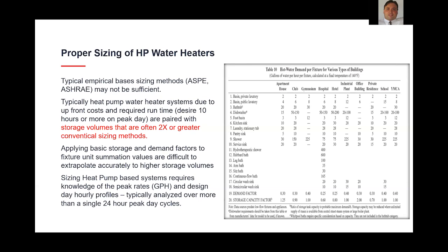And again, it's a twofold consideration, both upfront cost and the fact that these units typically aren't optimized for long steady state periods of operation at low delta T. Again, they're meant to come on, operate at almost full capacity, and shut off. So we don't want those cycling excessively throughout the day because they've been drastically oversized. So it's more analogous to load leveling an ice storage chiller. Your hot water storage tanks are basically your ice storage tanks, and your chiller's been replaced by these heat pump water heaters.